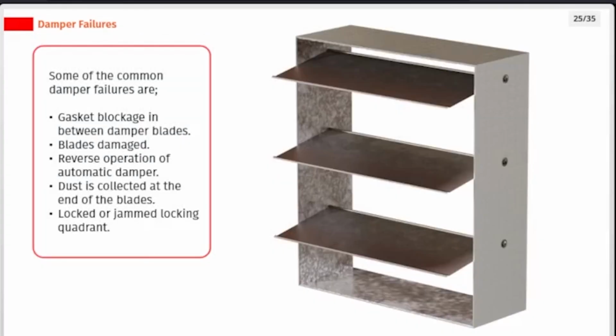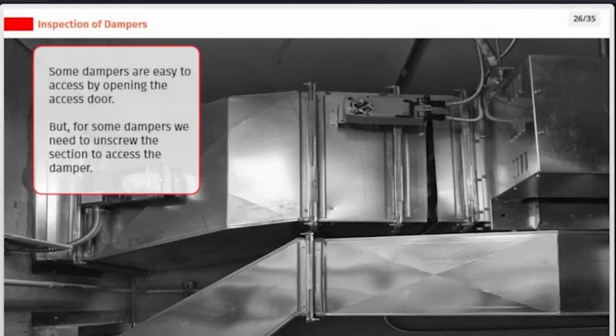Some of the common damper failures are gasket blockage in between damper blades, damaged blades, reverse operation of automatic damper, dust collected at the end of the blades, and a locked or jammed locking quadrant. Some dampers are easy to access by opening the access door. But for some dampers, we need to unscrew the section to access the damper.